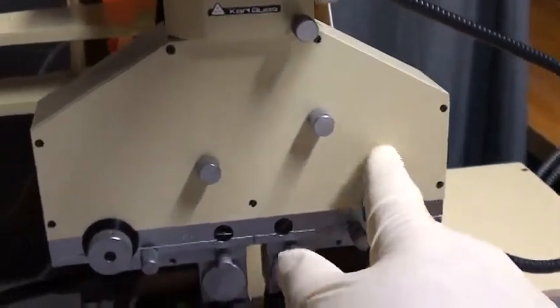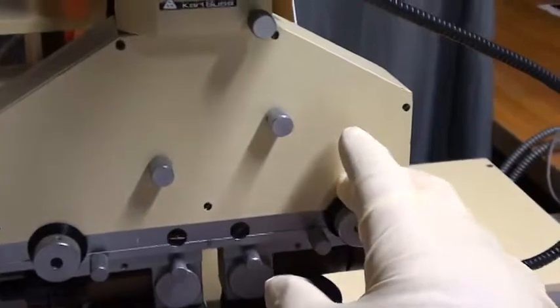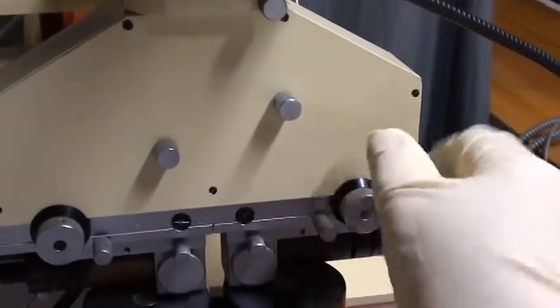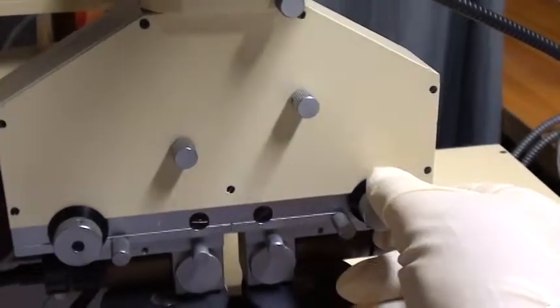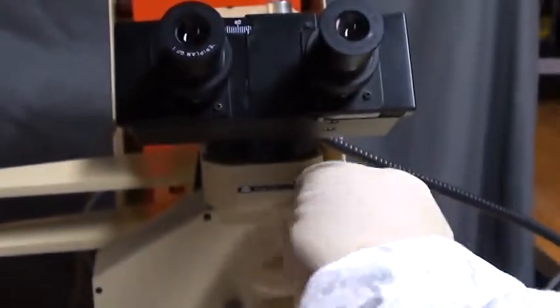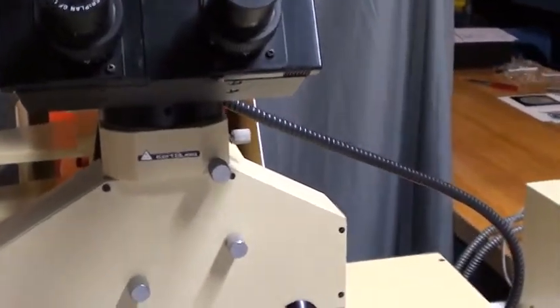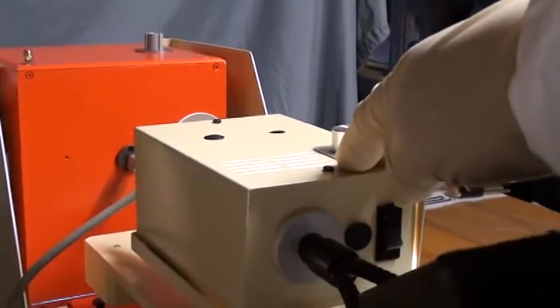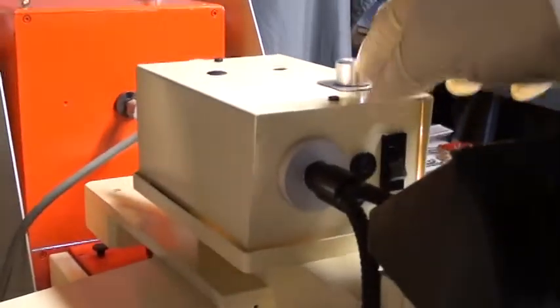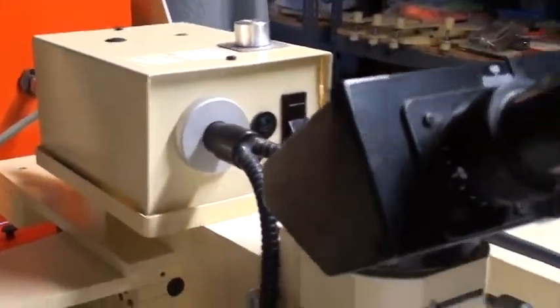The microscope has been disassembled, new bearings have been lubricated and put in, the slides and ways have been lubricated and cleaned. The rotation function of the microscope has been cleaned and adjusted for correct operation. A new lamp has been put in the 12 volt 20 watt illuminator. It uses a halogen bulb.